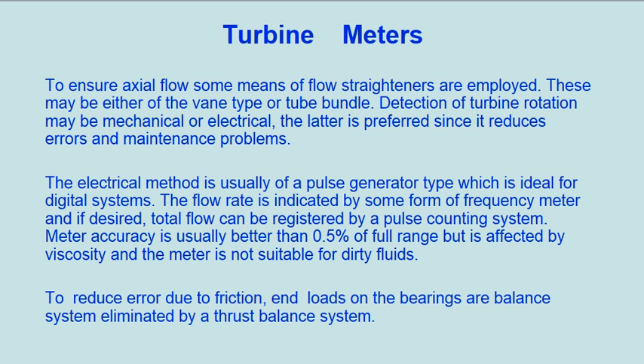To ensure axial flow, some means of flow straighteners are employed. These may be either of the vane type or tube bundle. Detection of turbine rotation may be mechanical or electrical, the latter being preferred since it reduces errors and maintenance problems.